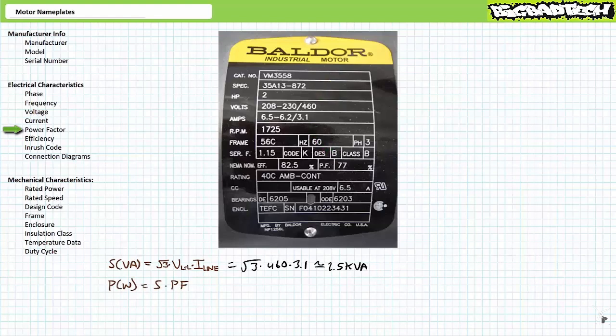Real electrical power in units of watts is equal to apparent power times power factor. This motor nameplate indicates this motor does so at a 0.77 power factor. Roughly 2.5 kilovolt amperes times a power factor of 0.77 demonstrates this motor consumes roughly 1.9 kilowatts of real electrical power input.